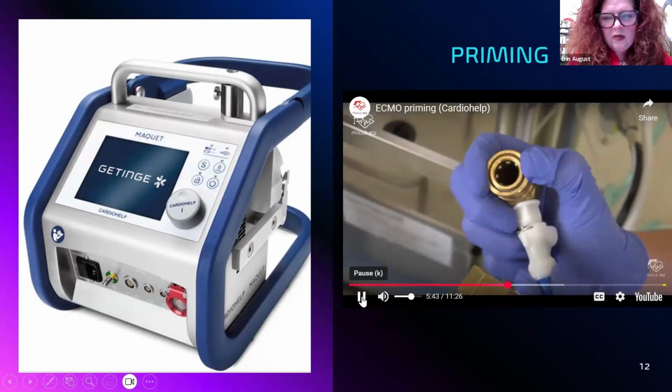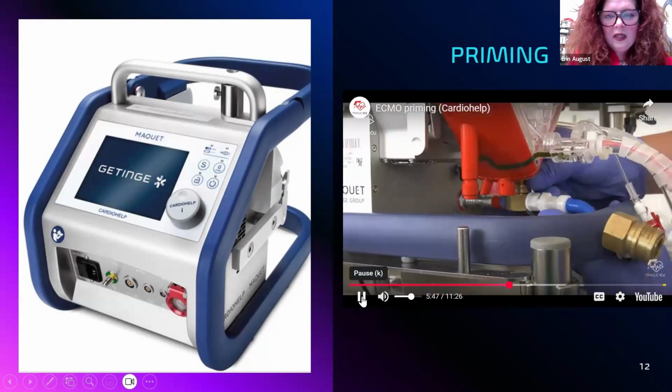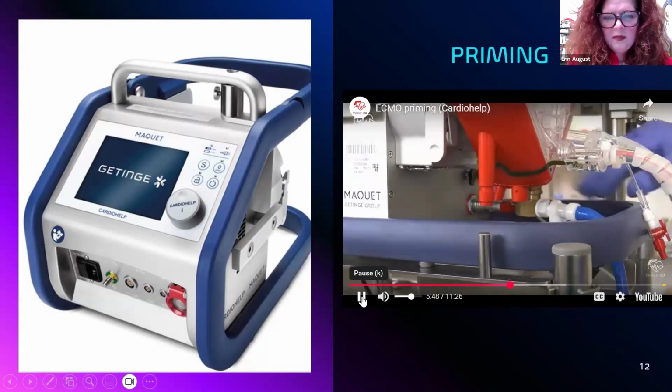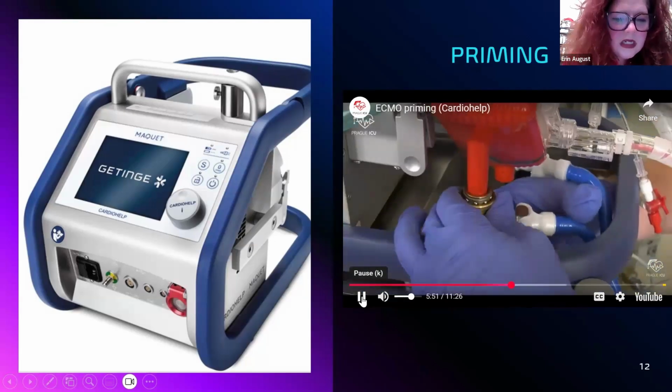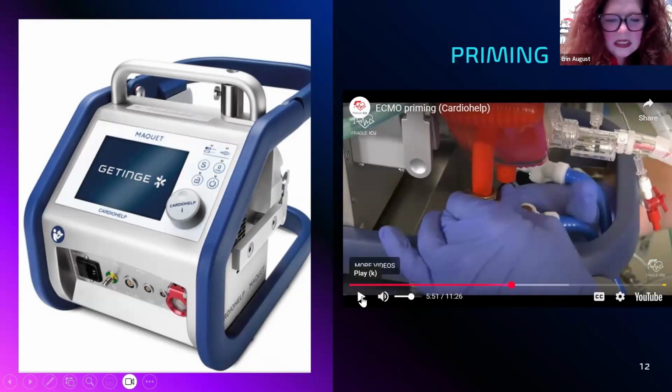So there's the connections that go on the bottom. Now, another important thing too, and I'll stop again when he puts the other side on. No, right there. When you're teaching your wet labs, here is another important thing to add as far as your heater cooler. Anytime you are putting your heater cooler on the bottom, you have to be careful of where you grab if you're having trouble pushing up on the bottom.